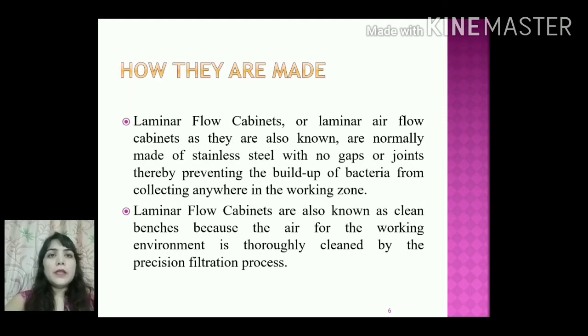So how are laminar airflow cabinets made? Laminar flow cabinets, or laminar airflow cabinets as they are known, are normally made of stainless steel with no gaps or joints, thereby preventing the buildup of bacteria from collecting anywhere in the working zone. So if any gaps or joints are there, the chances of microbial contamination will increase. So basically laminar flow cabinets are made up of stainless steel with no gaps and no joints. Laminar flow cabinets are also known as clean benches because the air for the working environment is thoroughly cleaned by the precision filtration process.